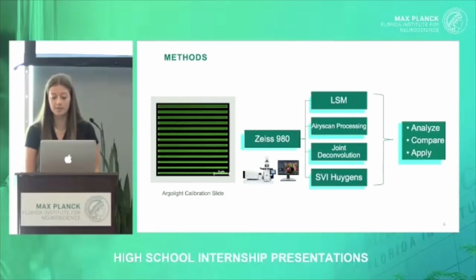In order to do this, I started by imaging the Argolight calibration slides to get a baseline and determine when the software was working the best. I imaged these slides on the Zeiss 980 Airyscan 2 microscope, and I used the 20x and the 63x objectives because these are most commonly used here for imaging. So the 20x is able to see a larger field of view, while the 63x is able to zoom in on a particular spot more clearly.